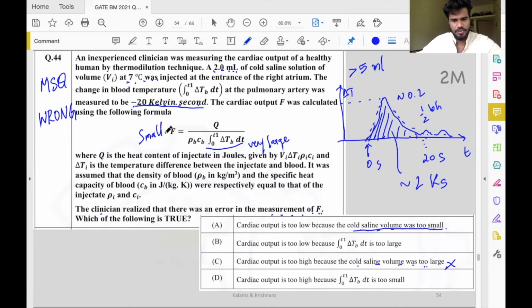So at this stage, what we can say is that the cardiac output is too low because delta T is too large. Okay. So this option is correct. And then we know the saline volume is too small, but we do not know whether it leads to low cardiac output. So at this stage, we cannot really conclude whether A is correct or not. I think according to the official answer key, both A and B are correct. There are lots of problems with this. As I said, we know the cold saline volume is too small, but from that we cannot conclude cardiac output is going to be too low.